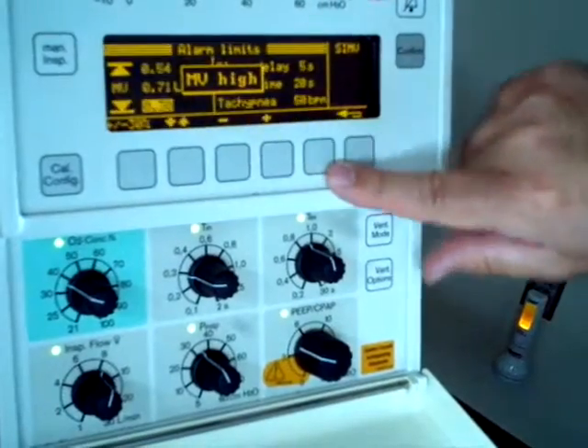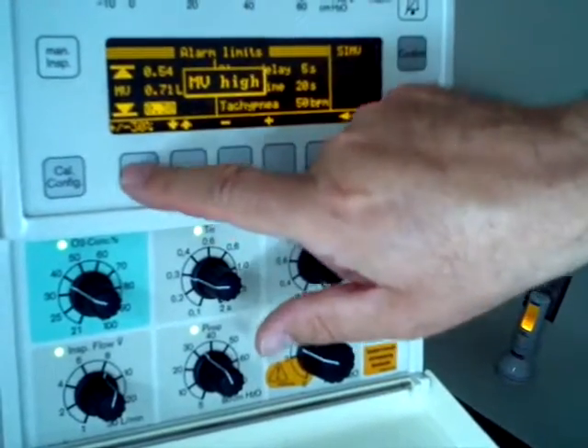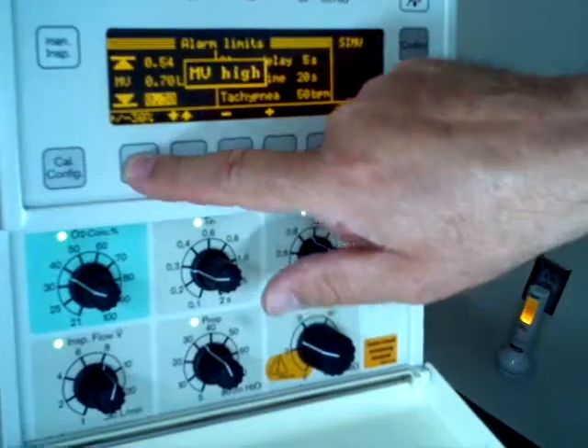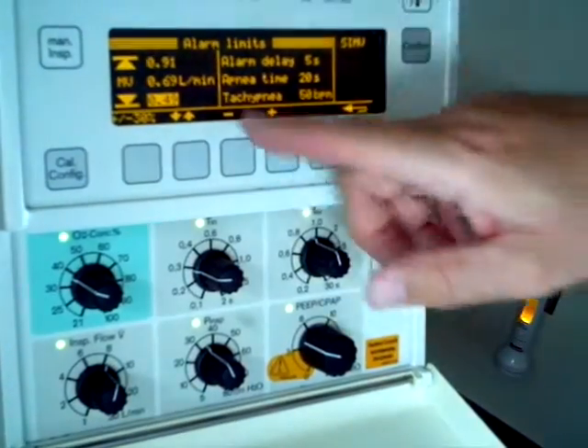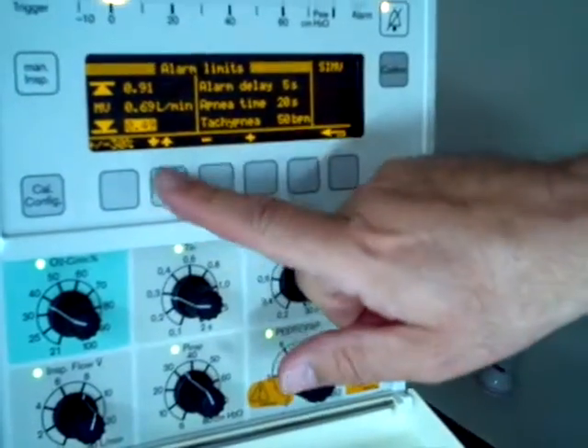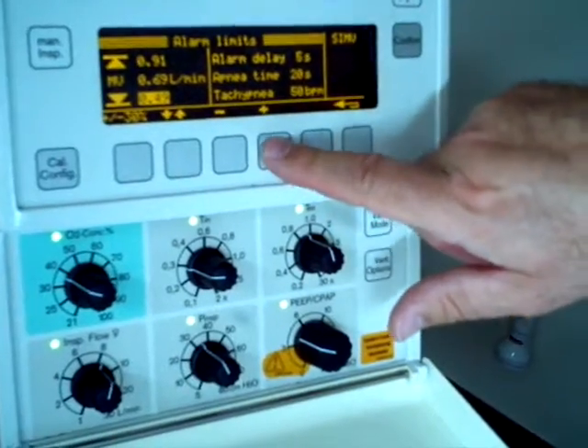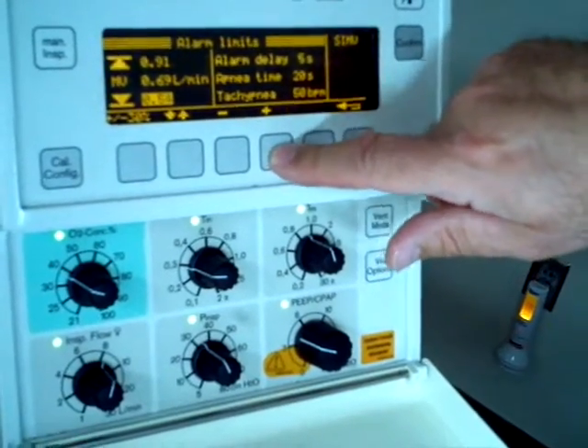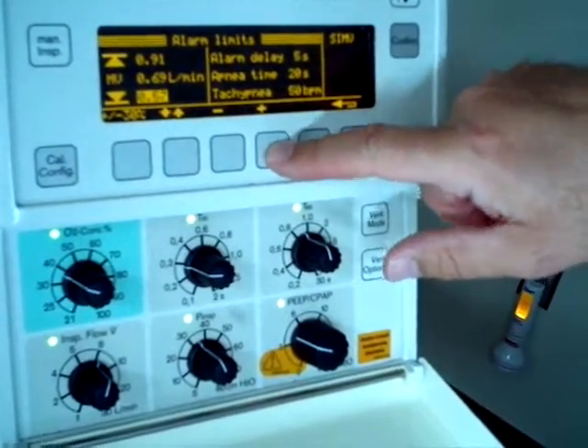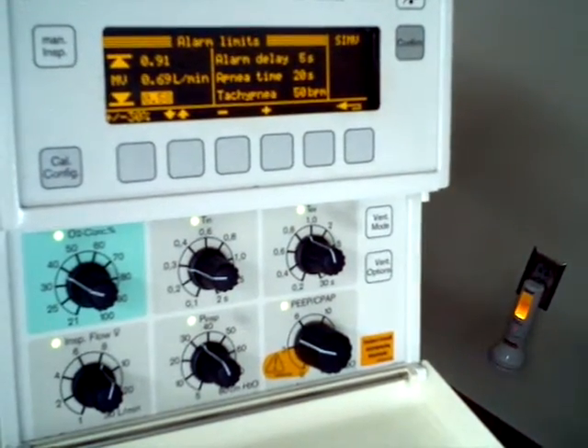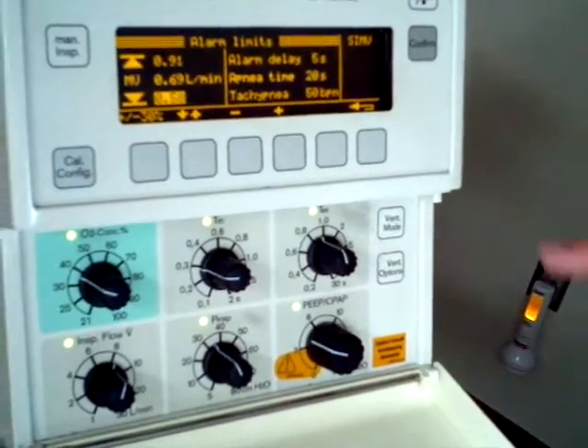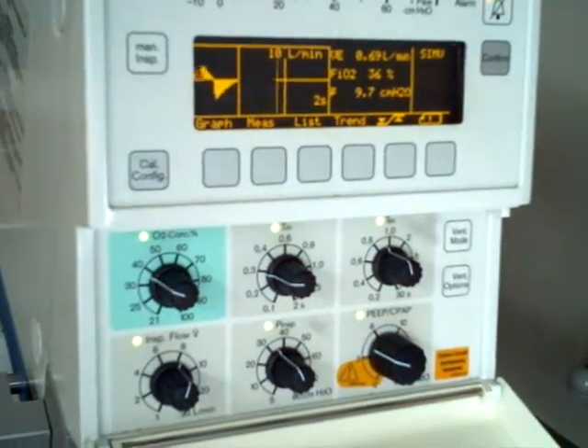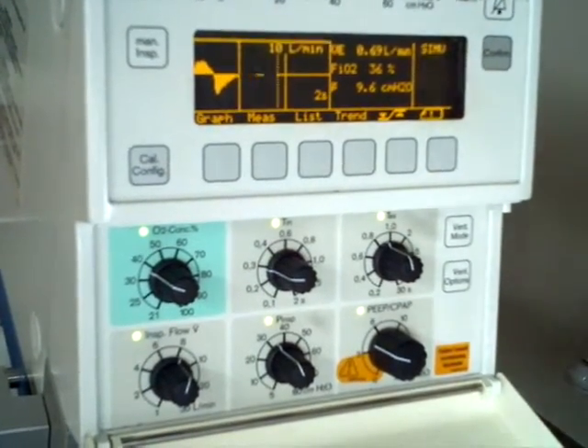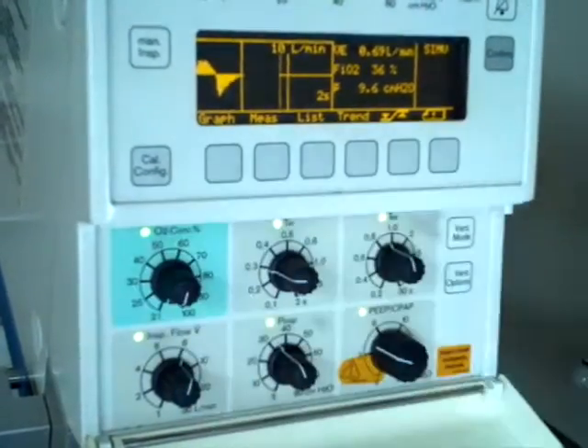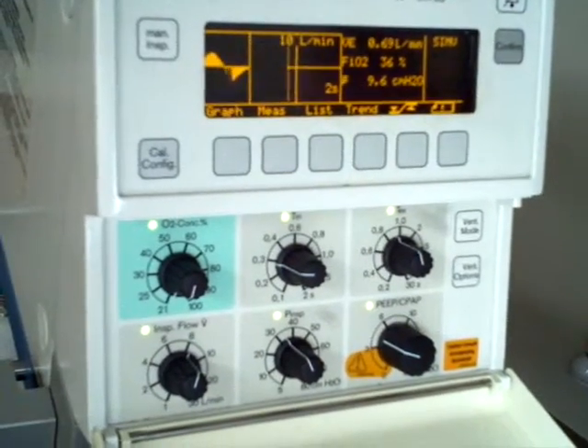It should be about 14. Catch our alarms again, look at our minute volume with a rate of 50 is really high now. We'll reset that. Not too bad. I might go up a little bit on the low minute volume just because we have a baby on a rate of 50. They're pretty sick. Let's set that a little bit tighter on the low side. That's a judgment call. Again, I'm going to turn the oxygen percentage down too, just to save oxygen.